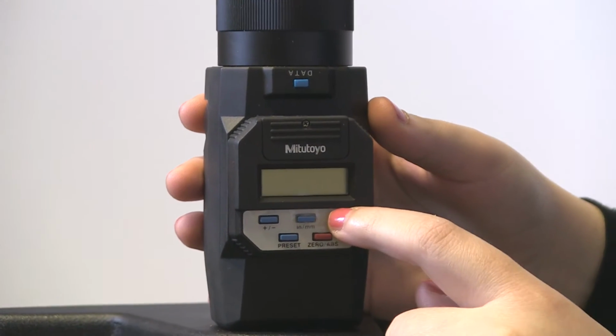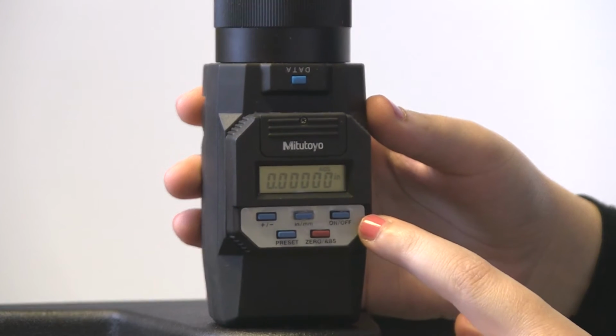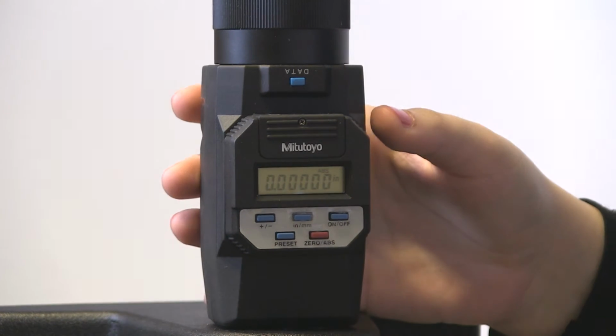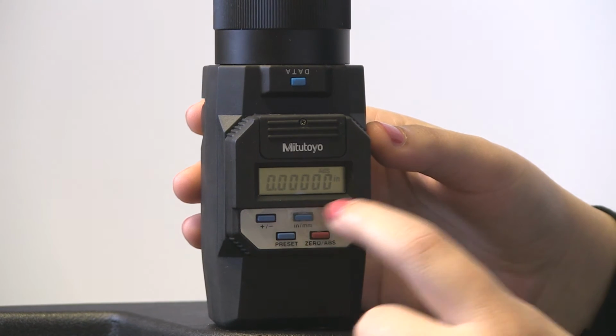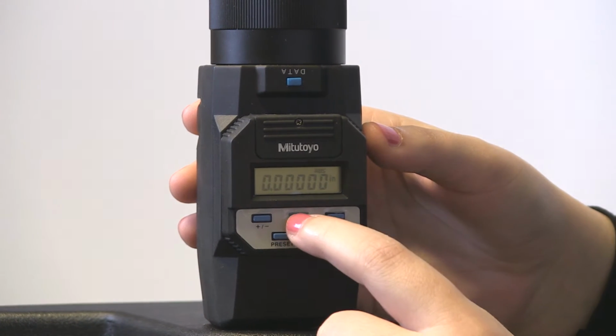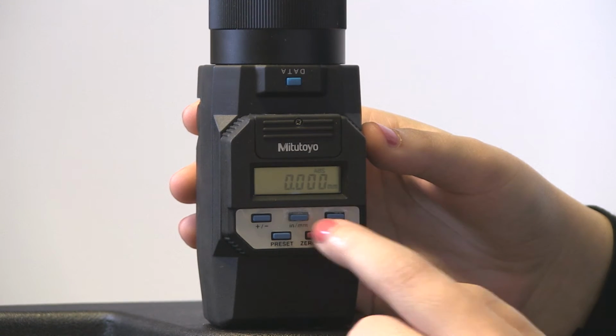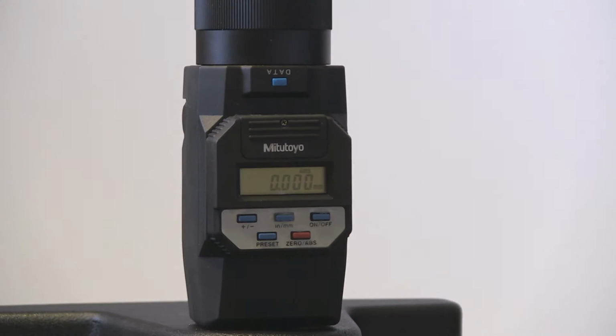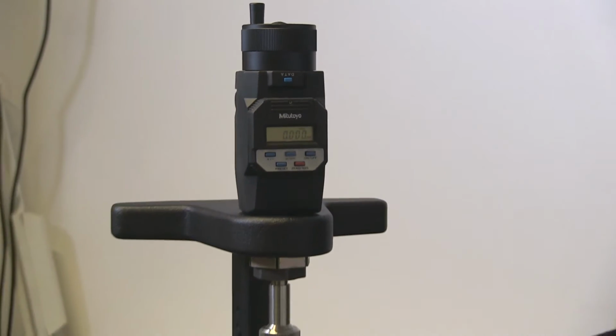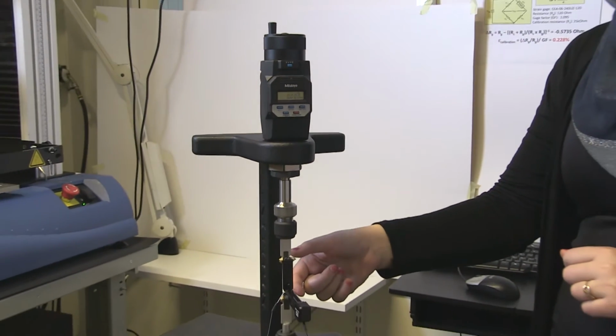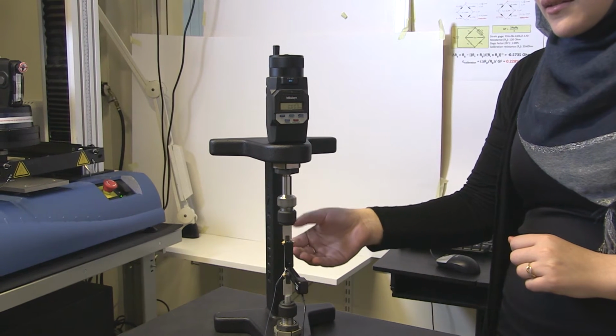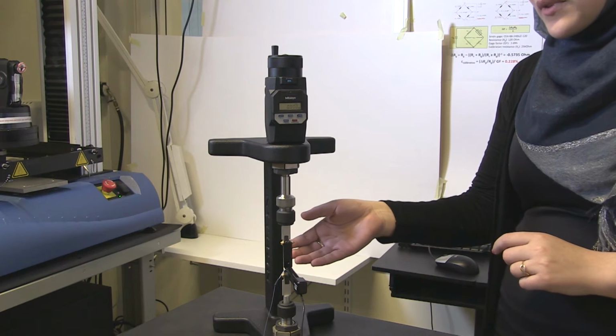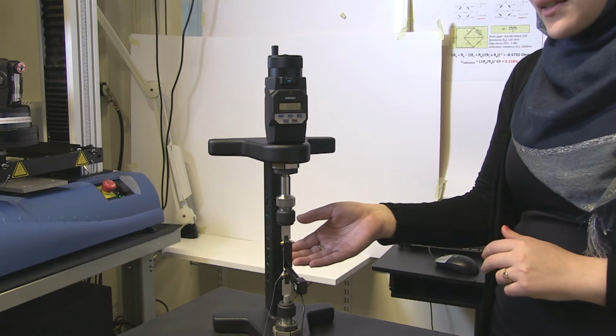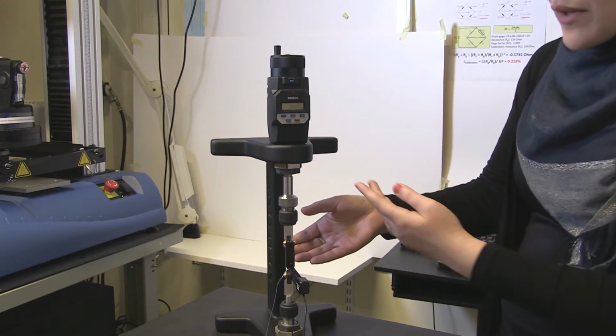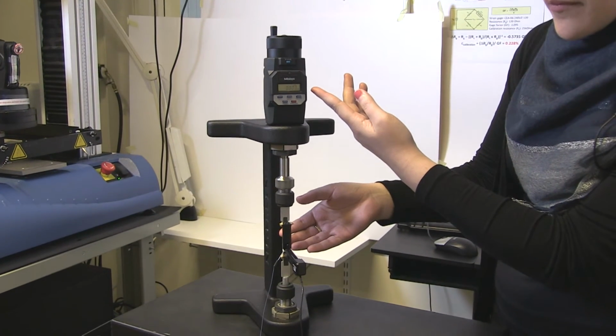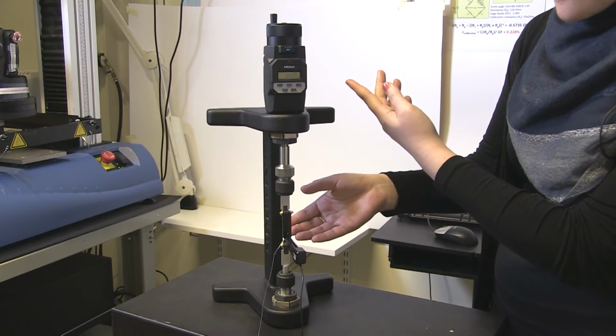You can switch it on with this button, and here you can read the value of the displacement. You can read it in inches or in millimeters, and we want it in millimeters, so we press the unit button here. The gauge length of our extensometer is 50 millimeters, which means 0.5 millimeter in this device will correspond to 1% of strain on the computer screen. And also, when we have zero displacement here, it should correspond to 0% of strain on the screen.